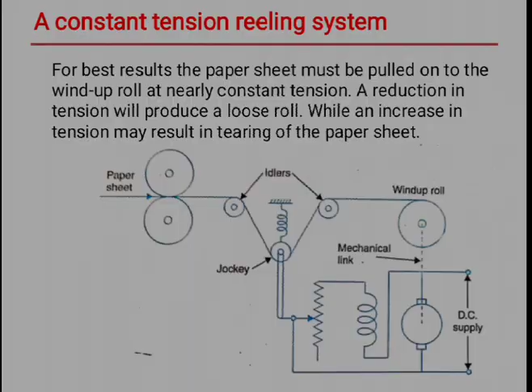As the roll is filled with paper, the diameter of the roll is increased, which increases the paper speed, which increases the tension. So as the tension is increased, this jockey moves upward. As this jockey moves upward, this arm moves upward, which cuts out the resistance. Because of the cut out resistance, the field current is increased. As the field current is increased, the speed of the motor is decreased. So the winding roll speed is decreased, which maintains the constant tension.